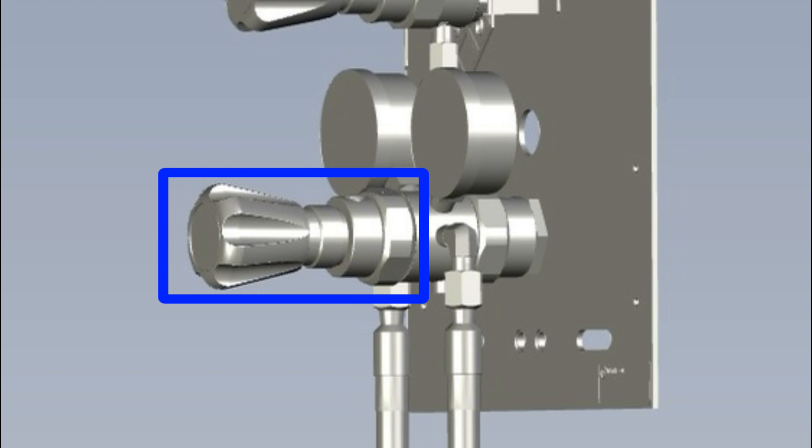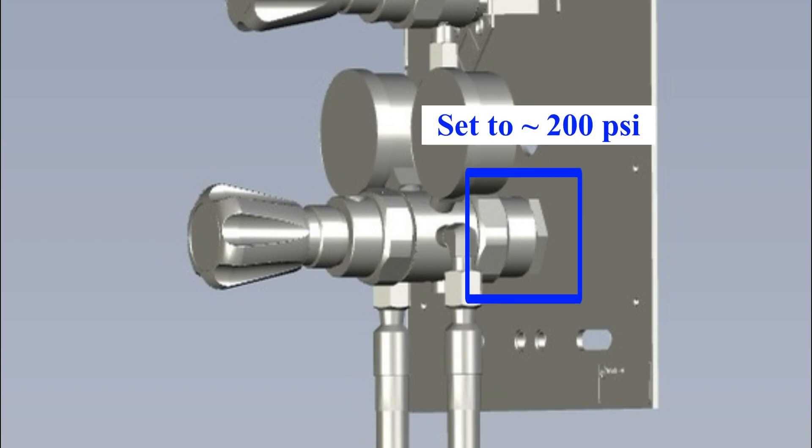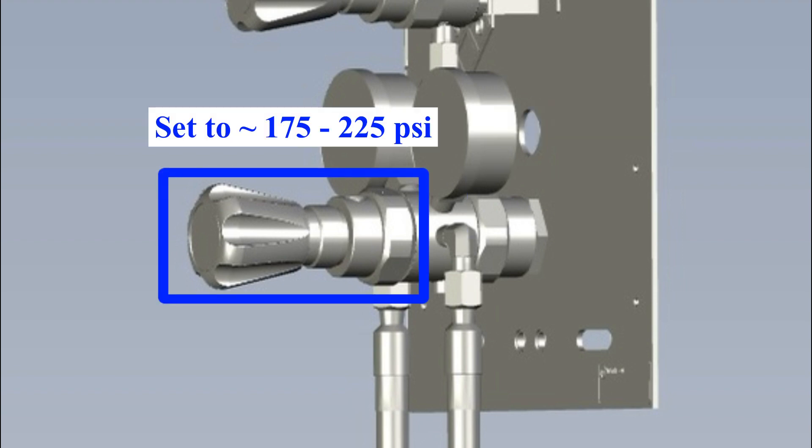The front regulator is for the gas source on the right side. The back regulator for most switchover systems is set for about 200 psi, and the front regulator swings from about 175 to about 225 psi depending upon the position of the arrow knob.